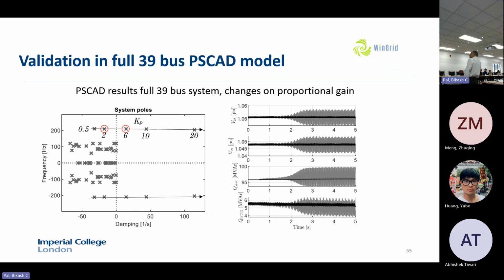And the PSCAD results: after we did all this for a simplified model, we now go to the full 39 bus system in PSCAD and put all those STATCOMs with the controller gain, etc. And then we do these simulations. And there you see the voltage at nodes 28 and 29, and the reactive power from the wind turbine generator and STATCOM, how they become oscillatory with high gain or fast response time of the STATCOM.